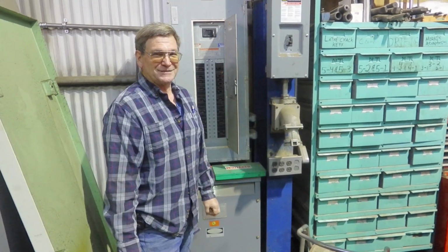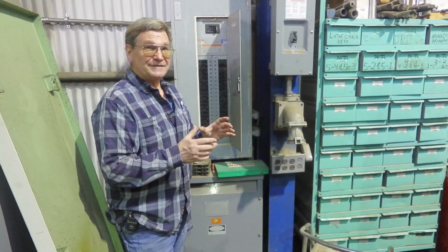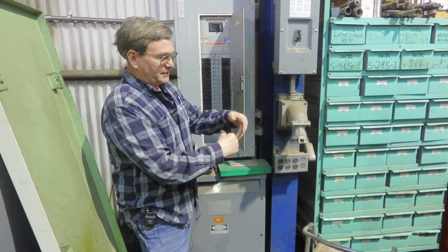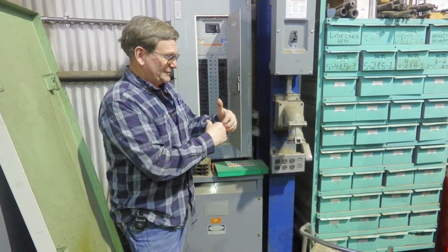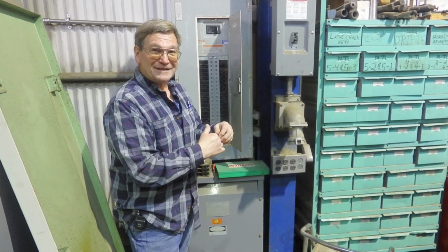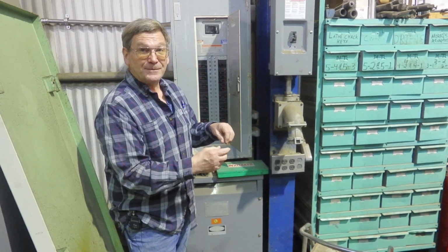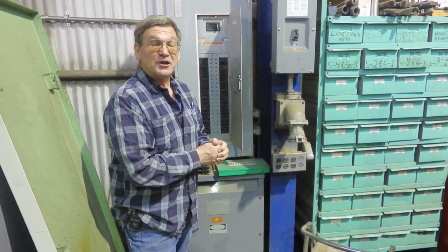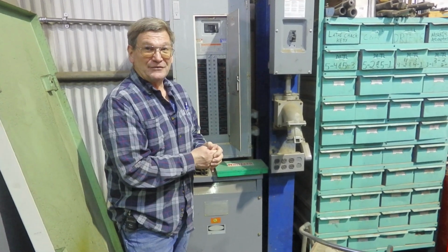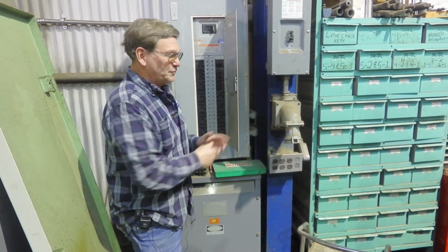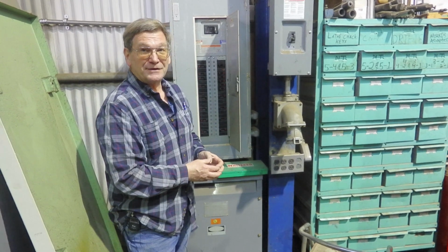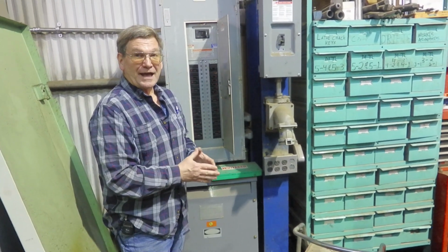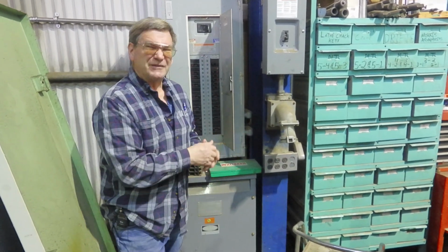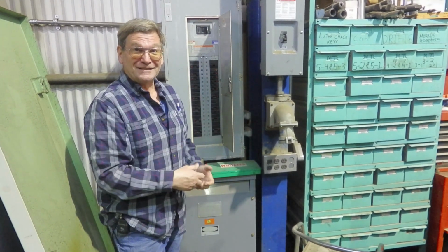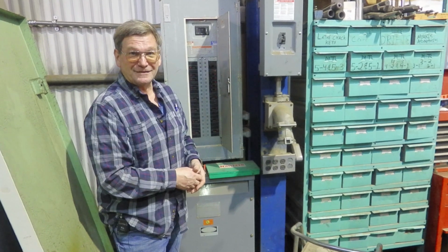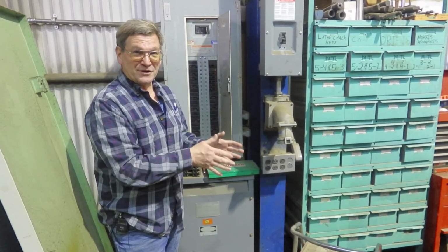There's always some variance. Point being, maybe we'll draw this on the board sometime, but instead of leaving those 3 coils connected in a Y configuration, I broke loose the center tap that was grounded. And I viewed these as 3 independent buck boost transformers. Now, if you take 480 volts and you connect to each of those 3 to be bucking your 480 volts, we'll just make it simple and call it 100 for the second. Instead of having 480 volts, you have 380 if we take 100 off of each of those by setting them up to be bucking transformer coils. So that would put you right where you want to be on the 380.